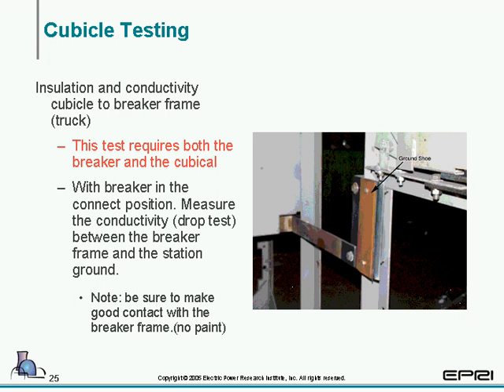Insulation and conductivity, the cubicle and breaker frame. This test requires both the breaker and the cubicle. What you're actually checking for is racking the breaker into the cubicle and seeing where the ground clip mates to the cubicle. You're going to check to make sure that the contact between the two gives you a low resistance. And when you're checking the frame of the breaker to the frame of the cubicle, you do not want to check it to any painted surface. It can actually lead to a false reading.